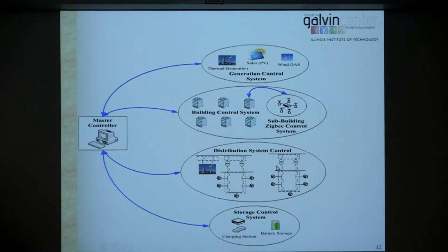Then we are islanded. Once islanded, we have to manage the frequency, the voltage, all the electrical components, and it gets to be an interesting venture. If you don't know what you're doing, the system can collapse right away. You have to know exactly how to manage the system electrically in order to keep voltages and frequency within permissible range. This device collects all the signals from PMUs, meters, building controllers, and sends the signals.